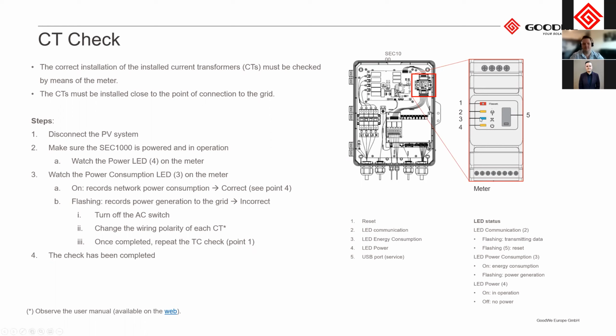Then lastly, the power, so consumption. When it's on, we are consuming energy from the grid. When that LED is flashing, we are exporting power. So it's very important to check that. If our PV inverters aren't producing and that LED is flashing, that means the CTs are incorrect as well.